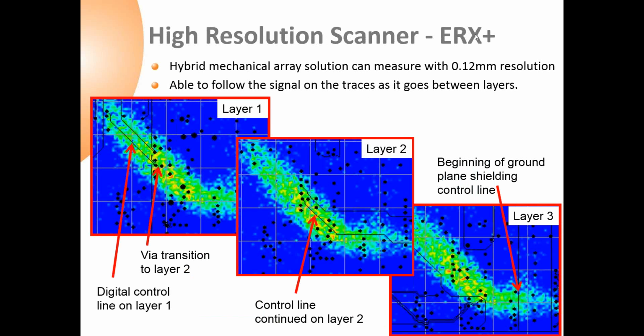Now, we mentioned that the fixed spacing of the array could be a limitation in some situations. What we've done is develop essentially a hybrid mechanical solution. We take that fixed array and put a small jitter on it, just fractions of a millimeter, allowing us to create essentially a synthetic higher resolution array. You can see this can now take us down to individual trace level, identifying specific vias that are possibly coupling energy. And you can actually track this through different layers of the board to follow where your energy is coupling through the design.